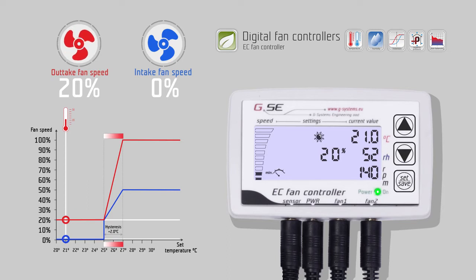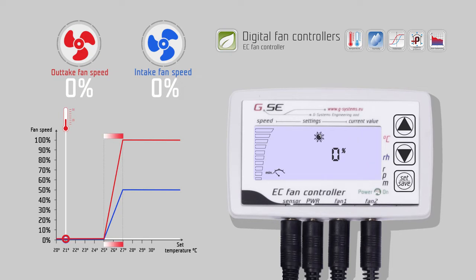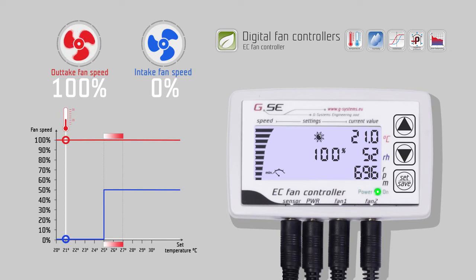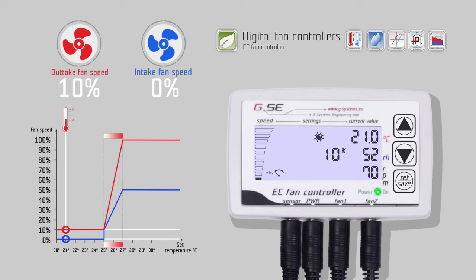If the value is set to 0%, the exhaust fan will stop working when the measured temperature or humidity are below their set values. The minimum speed can be set to up to 100% speed. For example, we set the value to 10%. Press down to go to the maximum speed day setting.